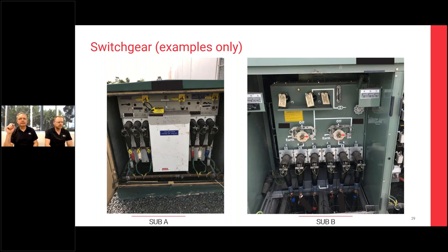One of the classic things, one of the biggest causes of failures of switchgear and on a whole HV assets is the termination failing. This is where the people are getting involved. This is where the stress control is very important. It's important how the terminations are made, how they're fixed on, particularly with these separable connectors. We've had issues where the alignment of the connectors is slightly wrong, causing discharge.